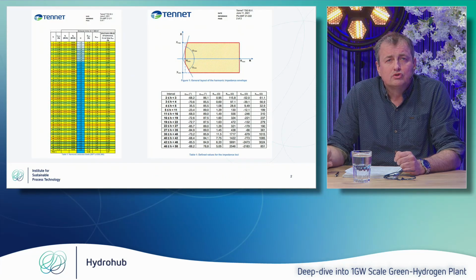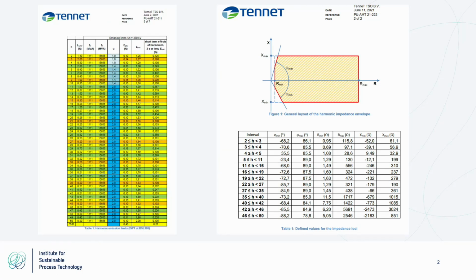Now, if you look at some input we got from TenneT, on the left picture you see that for each and every harmonic they have a planning level, which you see in the second column. There you see the planning level for each and every harmonic. And at the bottom of that table, you also see a limit for the total harmonic distortion at the point of evaluation, at the point of connection at TenneT, at the 380 kV.